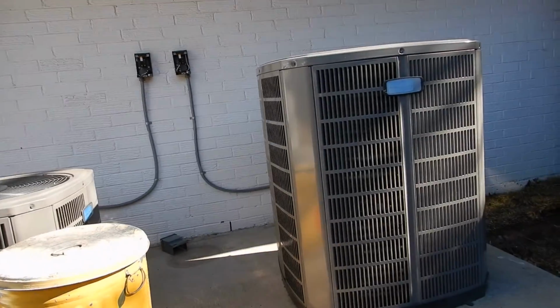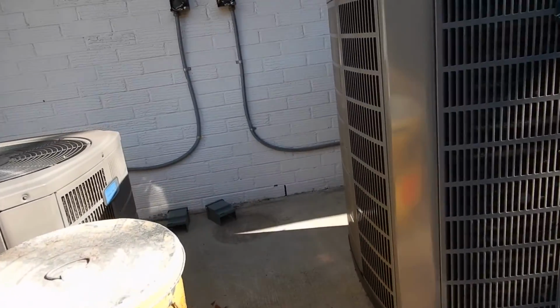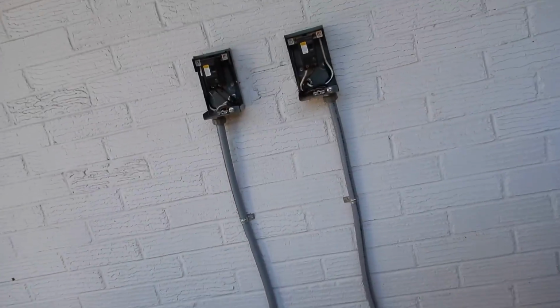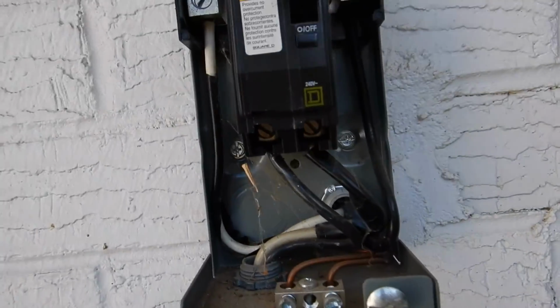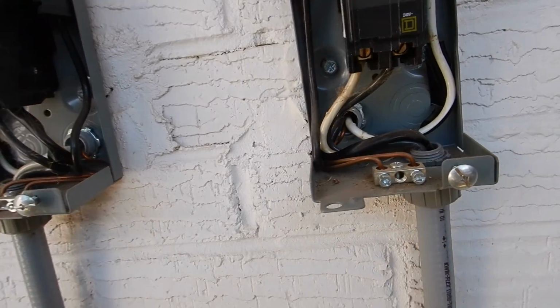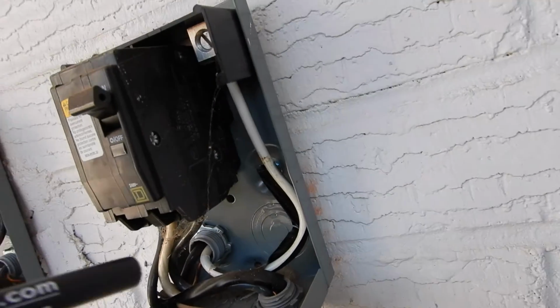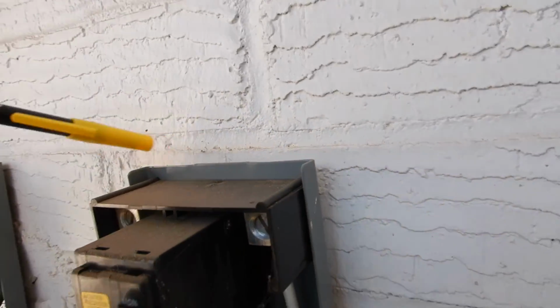These are the condensing units. These are the electric service disconnects on the backs of the units. They're laced up pretty good. It looks pretty nice. These should have been sealed, like the electric service panel, the electric service disconnect, and the electric meter. These boxes should have been sealed on the tops and the sides to help prevent moisture from going back down into the system.